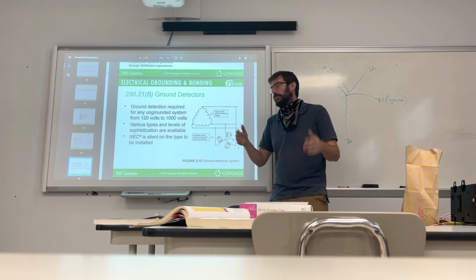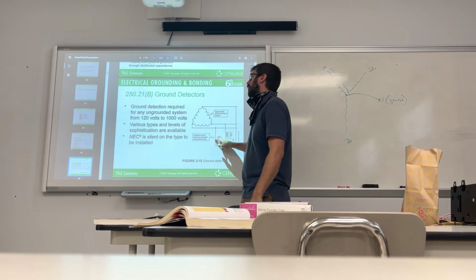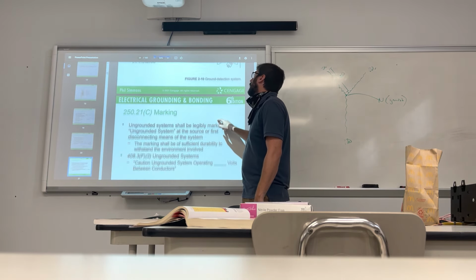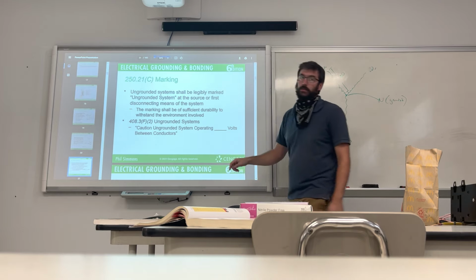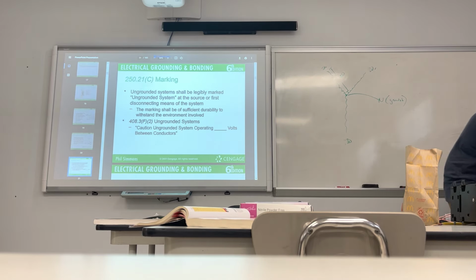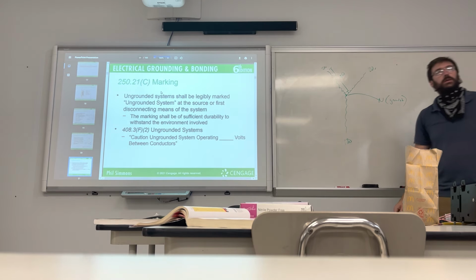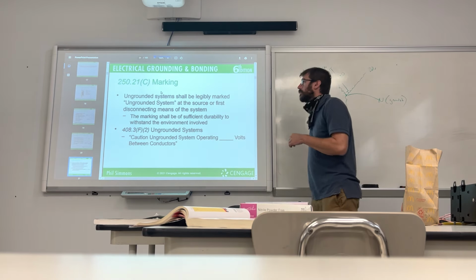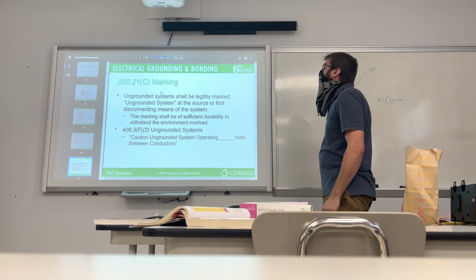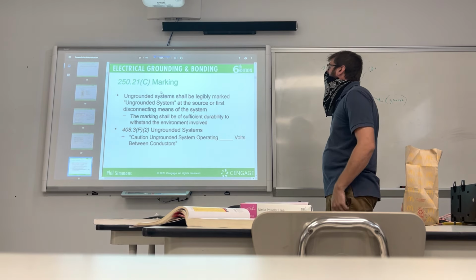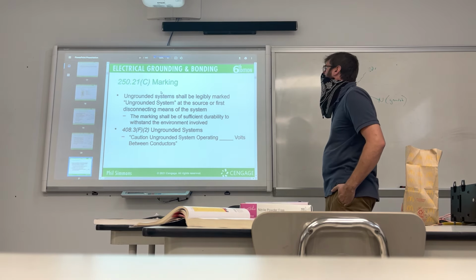You know what I mean? So it's going to be a risk and reward type of deal for those kinds of systems. But once again, I can't stress enough, they are few and far between. You guys will not be hooking them up often, if ever. Who's up? 250.21(C). Marking. Ungrounded system shall be legibly marked "ungrounded system" at the source or first disconnecting means. The marking shall be of sufficient durability to withstand the environment involved.